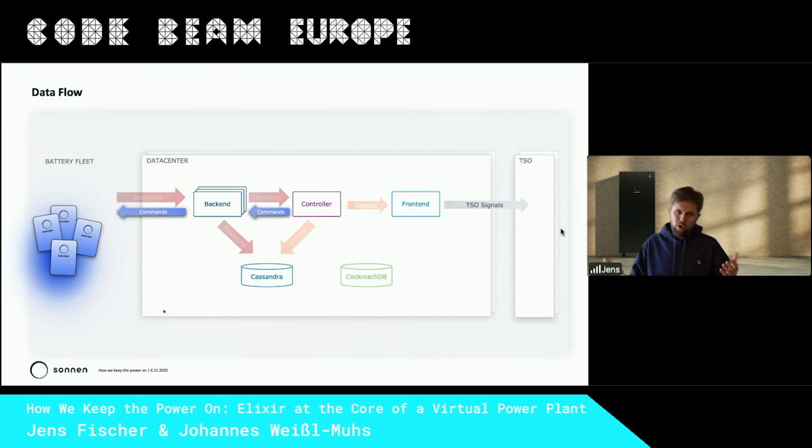These reactions are all reflected in the readouts, because the battery measures what it's doing itself. And these readouts are sent back again, and in turn inform the next round of commands. So through the readouts and the commands, the controller and batteries together form what you could call a distributed feedback control loop.